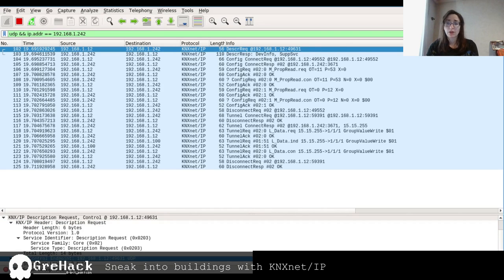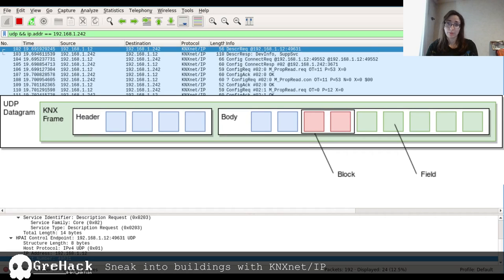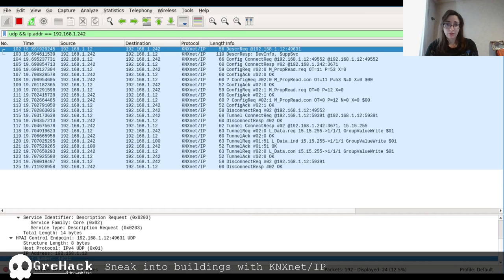For example, this frame is a description request sent by KNX map to request the server to describe itself. KNXnet/IP frames are usually sent over UDP, and the structure of frames is quite complex. The format, order, and content of blocks and fields in the body change for each type of message that can be carried by a KNXnet/IP frame. There are KNXnet/IP-specific frames, especially for device discovery, KNXnet/IP connection and configuration, and other types of frames that embed raw KNX frames to transmit to devices.